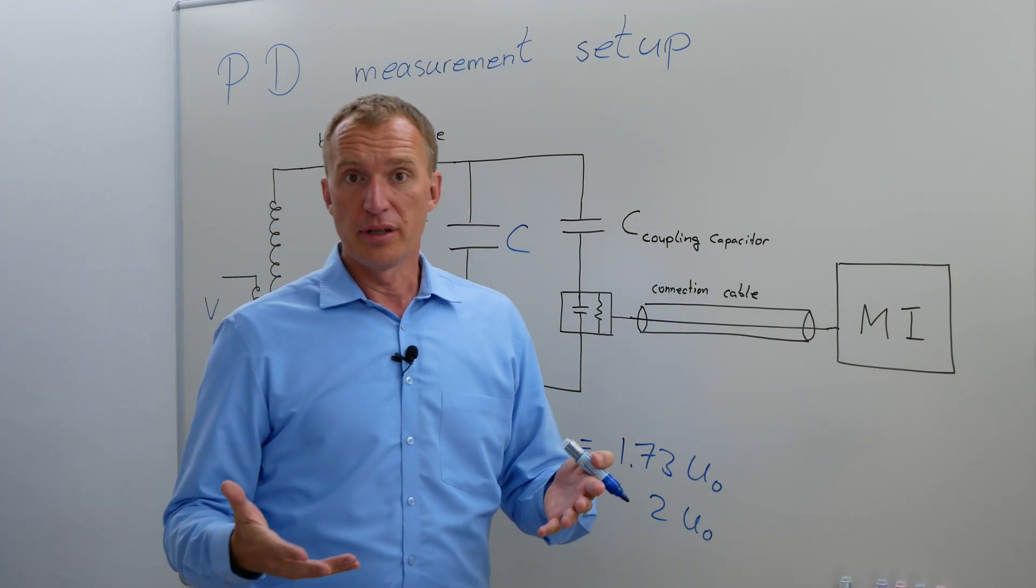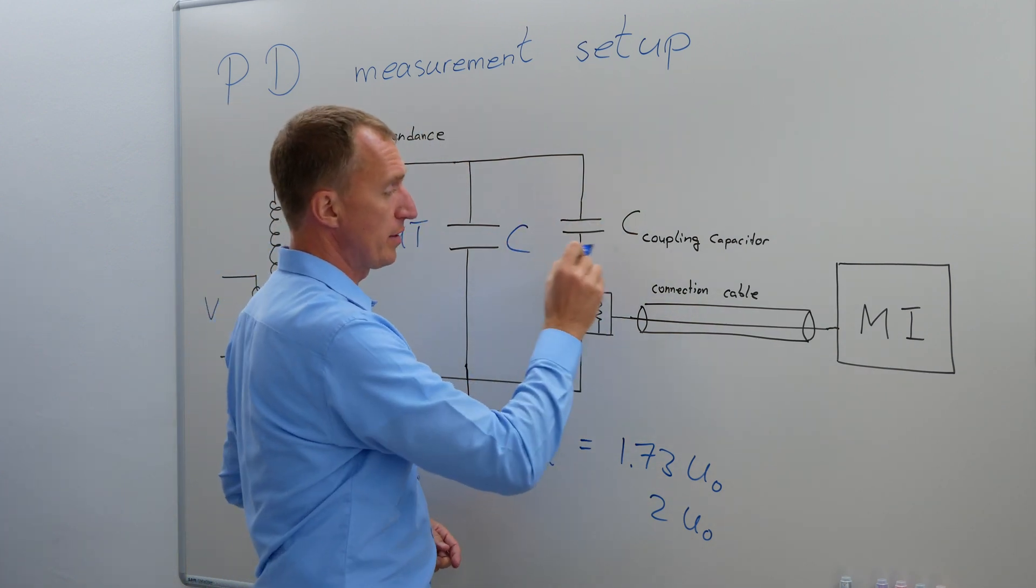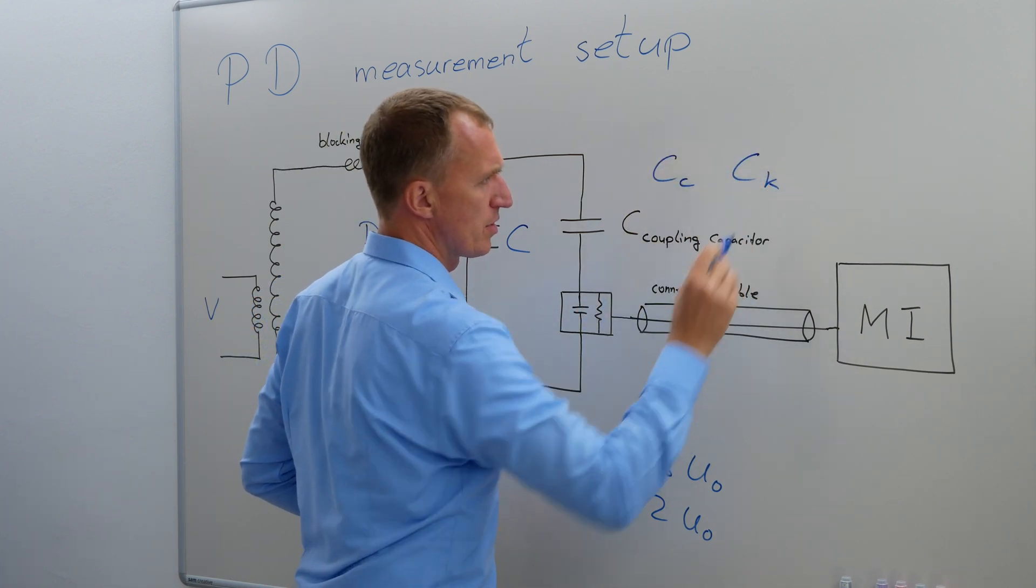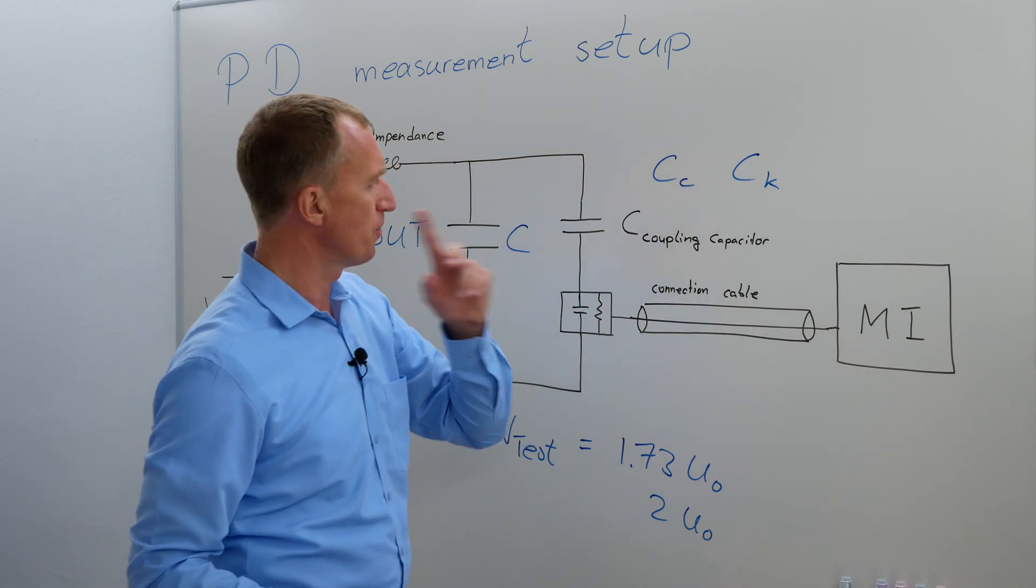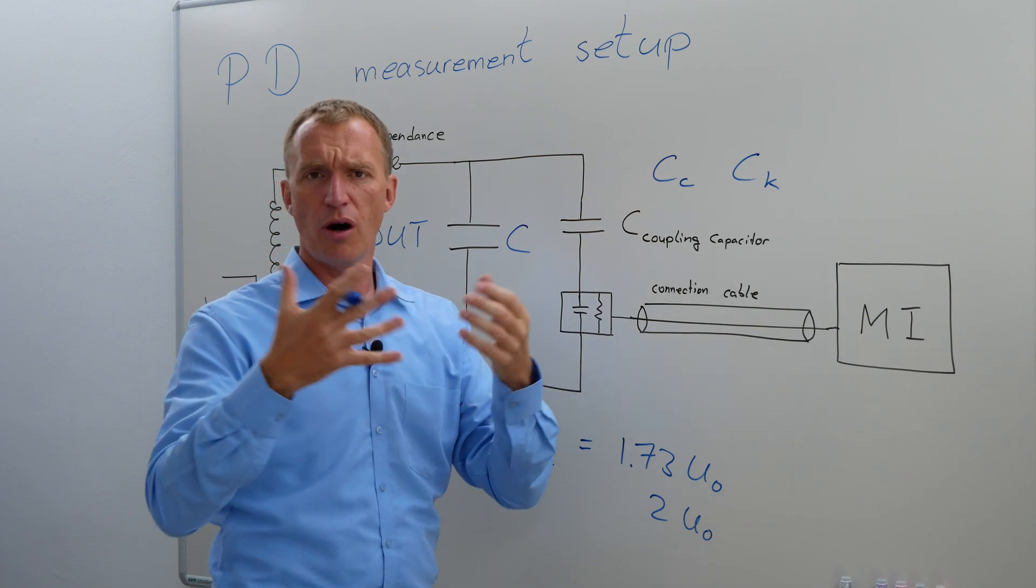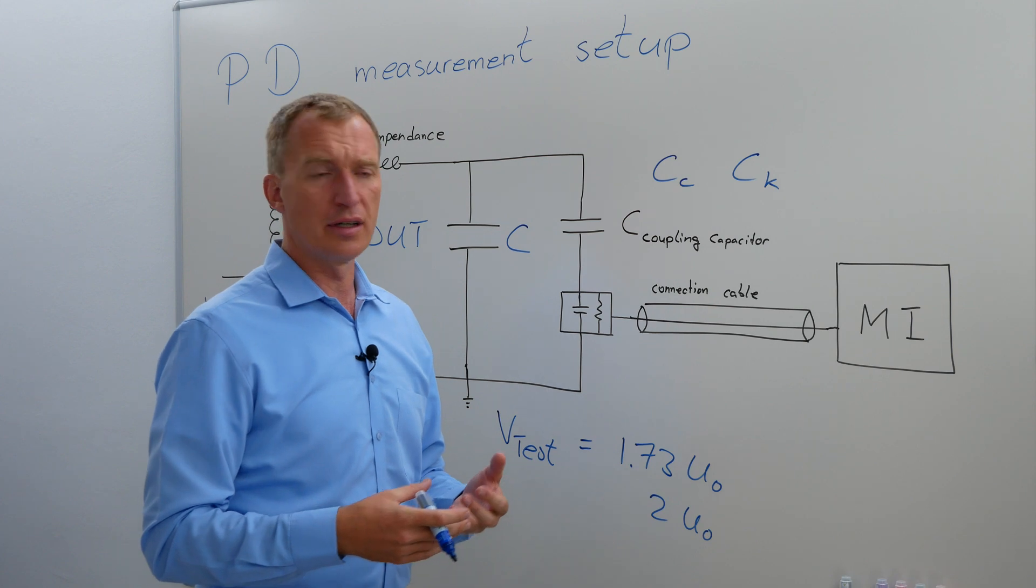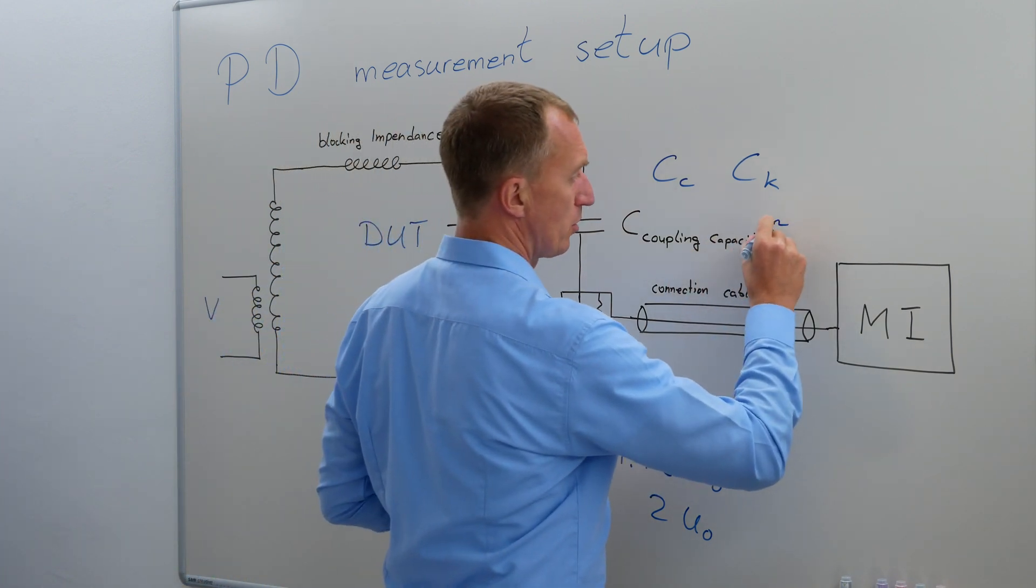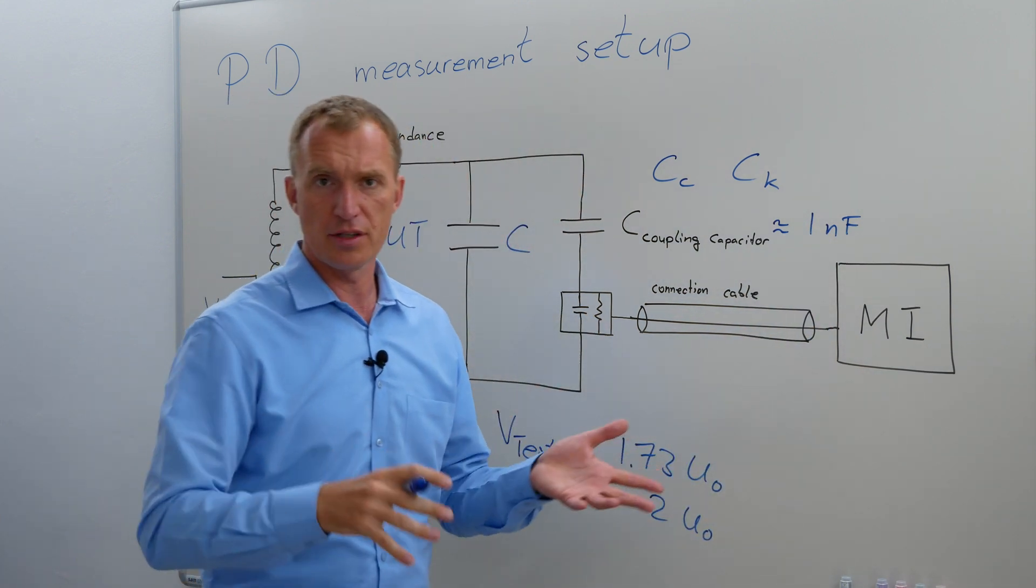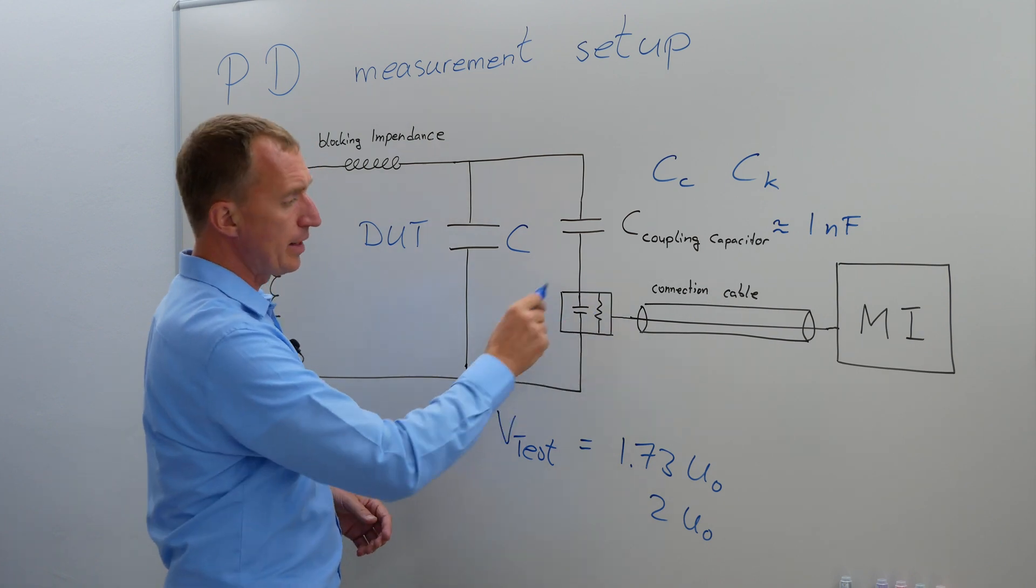This connection device could be a capacitive divider. Here it is displayed, this would be a capacitance with C, very often abbreviated as CC or sometimes CK, at least in the German version. This stands for coupling capacitor. The coupling capacitor very often is a capacitor that you buy from somewhere and it's not uncommon to have a coupling capacitor of about one nanofarad. They can be bigger or smaller, but one nanofarad is a pretty common value.